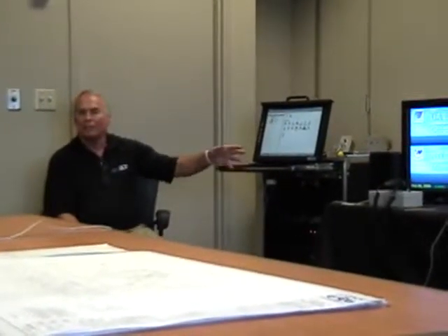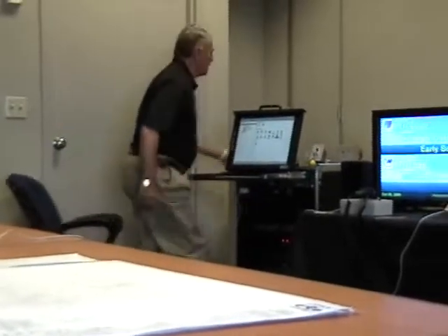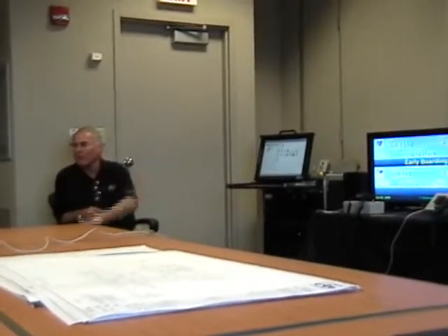The music you heard was fed into a little box like this. We use those a lot. A lot of these food courts have them. You put them in food courts, you put them in gift shops where they want to play their own music, yet we want to have speakers and all in there so that if we have an emergency announcement, we override their music. That runs on standard Ethernet cable. It's not Ethernet, but it comes into the back of one of the boxes. Then this way they can plug their own CD player, their own music in, got their own volume control, and we just duck it when all that happens. So if we need the system, we got it.